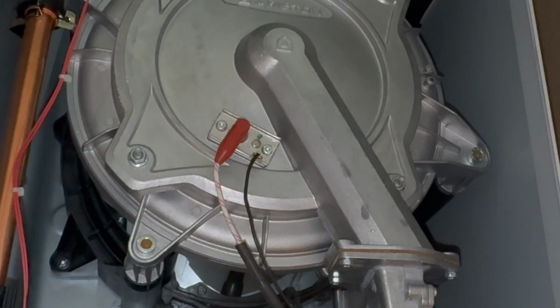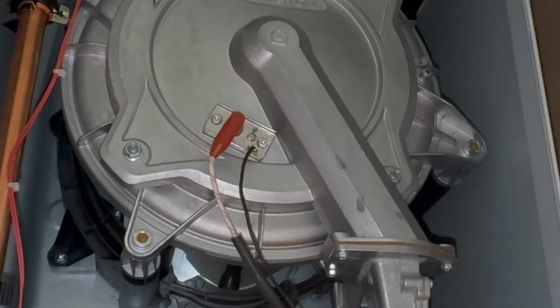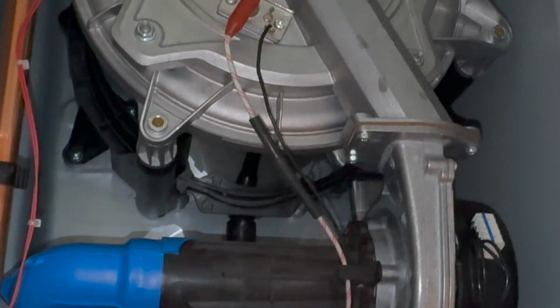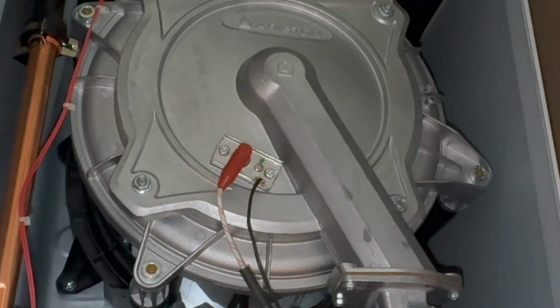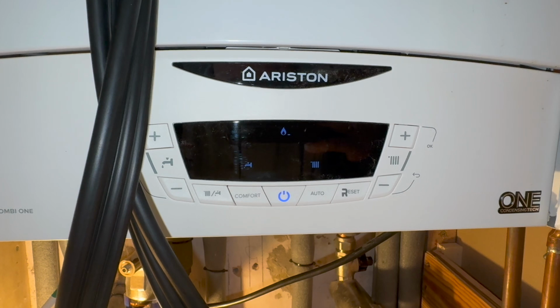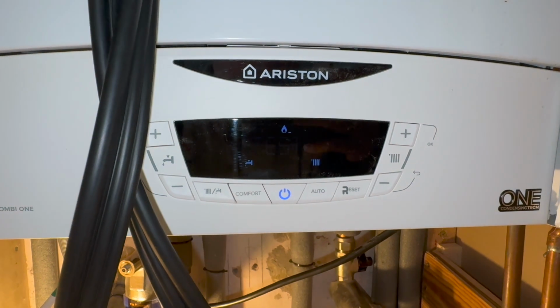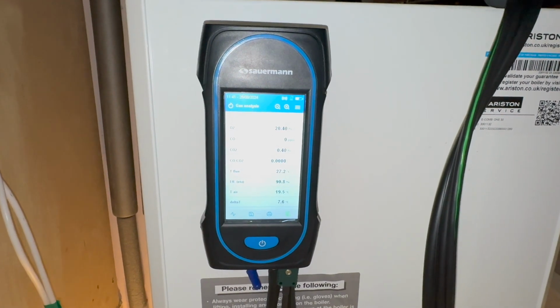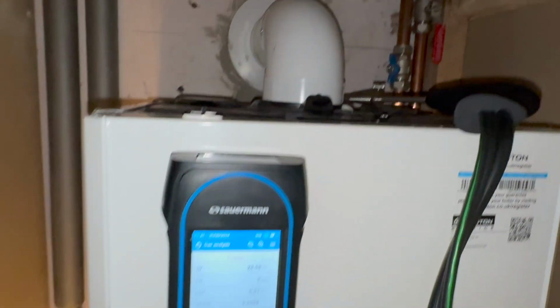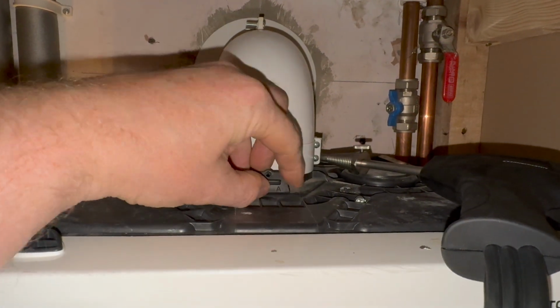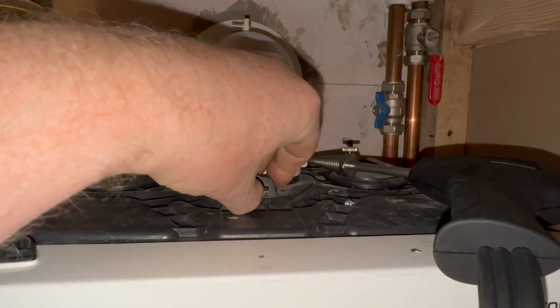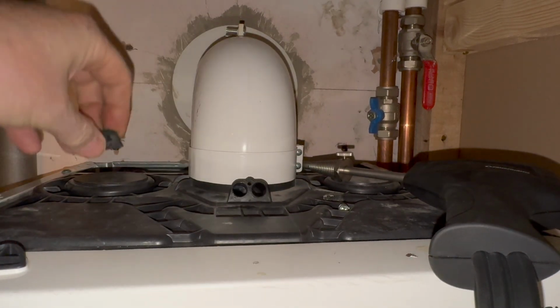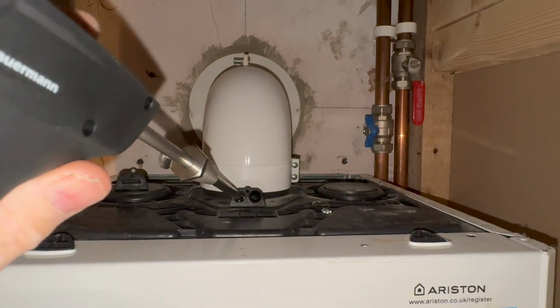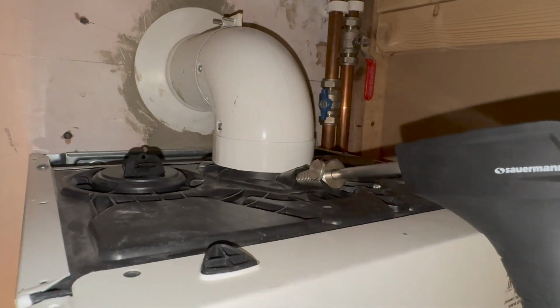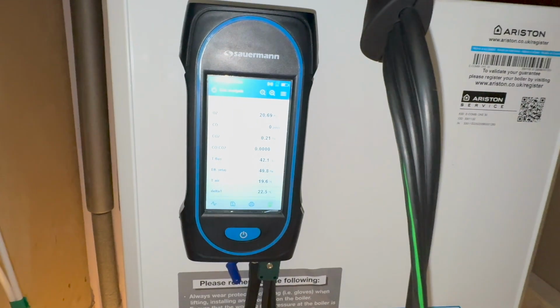So what it'll do now is it'll circulate the water around the heat exchanger and the plate to plate to get rid of all that air you can hear in there. Now I've got this boiler in test mode and I've actually got it in low setting, you can see that there. So I've got my Sauermann Si-CA 130 analyzer all ready for going. Now this boiler has been running for about 10-15 minutes. I've taken the screw out already from the test point. So I can now put the probe in this left hand side and I can now see what the readings come out at on this analyzer.